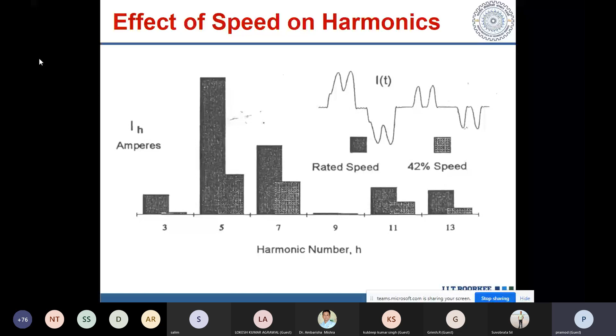But if you put some choke in series with this, then the harmonic spectrum is improved. This is without any choke. This is with some percentage, 3% of the transformer impedance, put here. Now in this case, without choke, you can see the THD is very high all throughout. But if you put a choke, then the THD is drastically reduced.